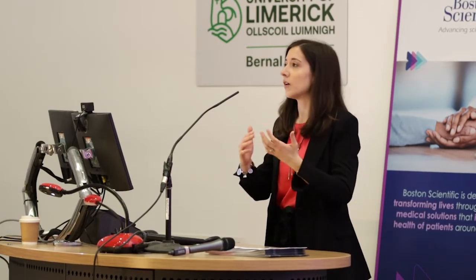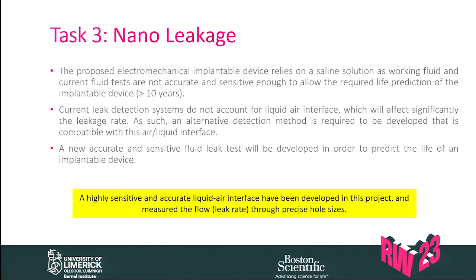Finally, the last test was to detect nano-leakage. So in case small holes are forming in the device, how much liquid are we losing and how long will the device last? This was probably the most challenging test. The key issue is that current leakage tests are done with gases, for example helium testing. And this is not good for us because it doesn't give us the correct sensitivities.